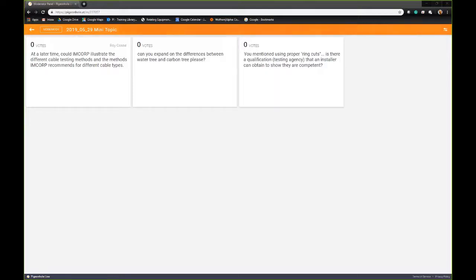So today, when we started getting into the renewal business, a 35 kV cable is not very forgiving. So those cables weren't lasting very long. 100% load, 90 to 100% load, 35 kV class. So an imperfection in that ring cut was going to show itself pretty quick. It could last a week, it could last 6 months, but it would ultimately fail.